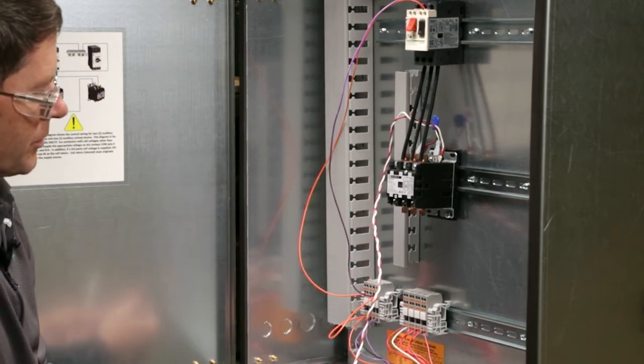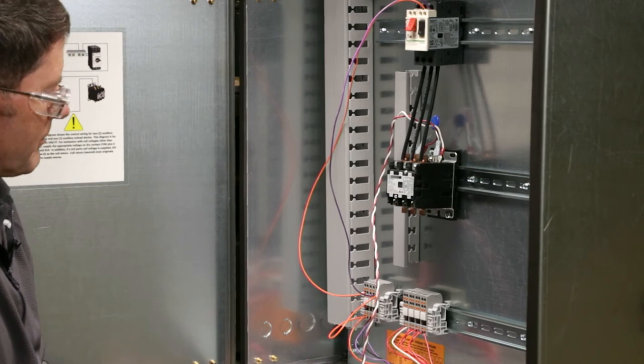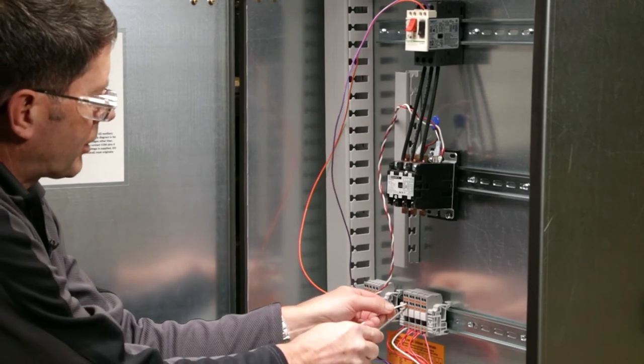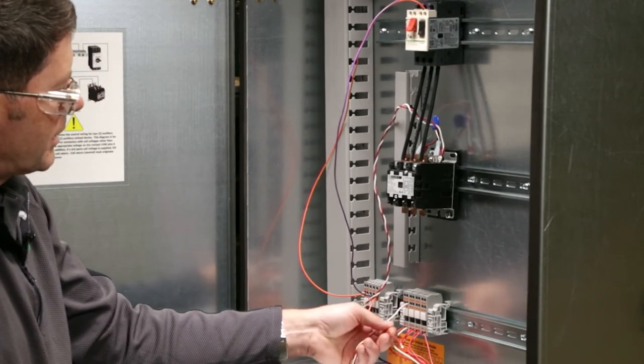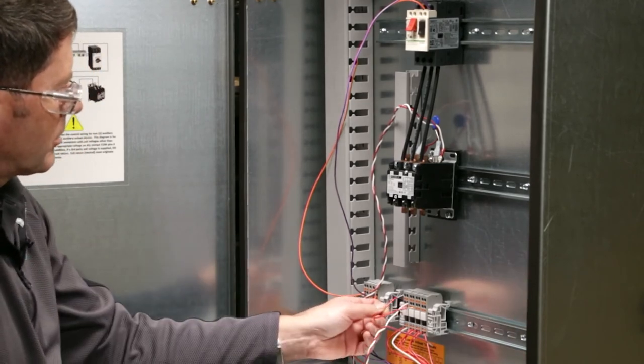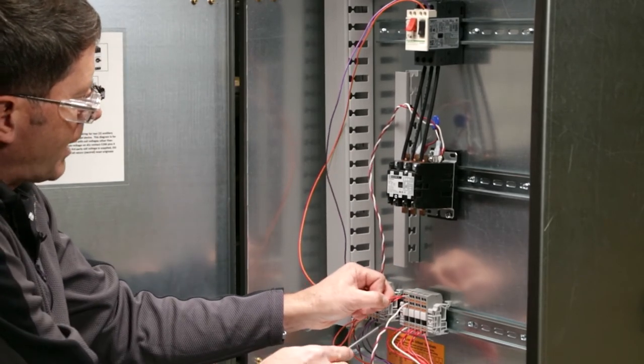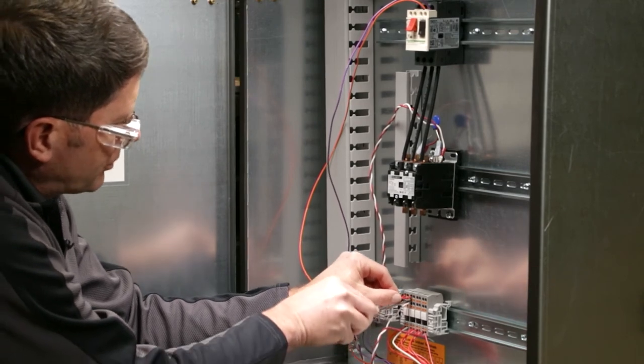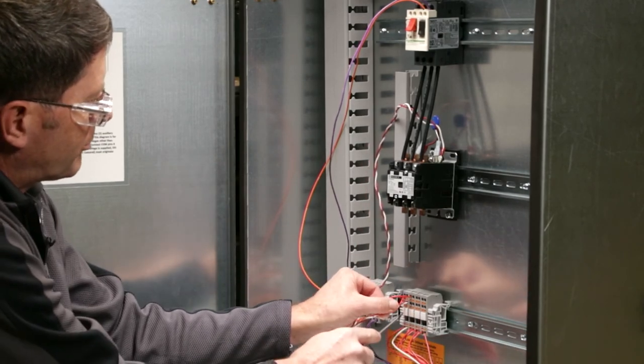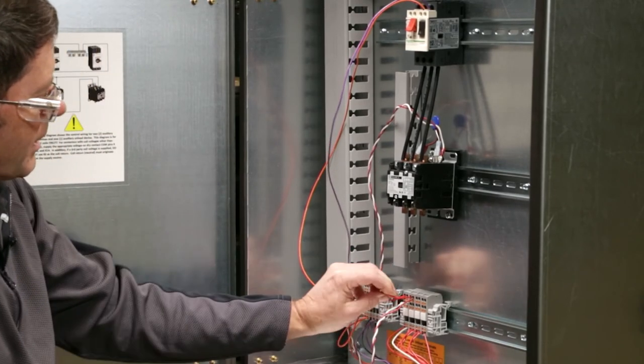The next thing we'll need to do is if you're using our 120 volt power to energize the coils, we'll need to take the neutral, which is our white wire and put it in circuit number two. And then we'll need to supply power to one side of our dry contacts. We'll need to take power from circuit number one, which is our 120 volt power. And we'll need to supply it in this case to circuit five, which is one side of the dry contact. Then we'll need to take the other side of our coil power and put it into circuit number seven.